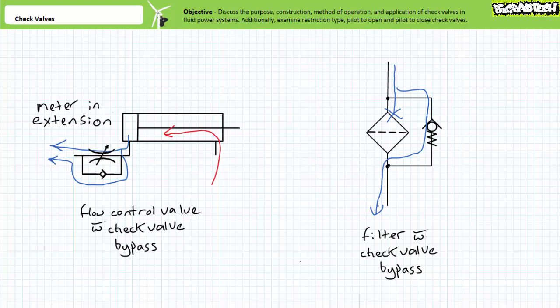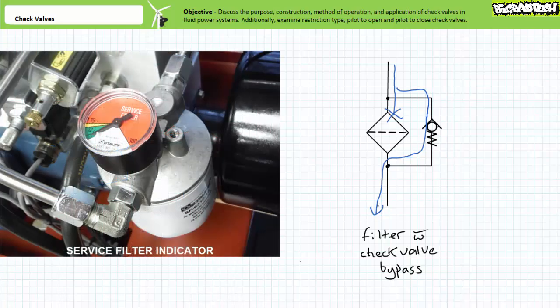The clogged filter bypass check valve therefore allows the system to circumvent the compromised fluid conditioning apparatus and initiate an orderly shutdown. Note the clogged filter bypass check valve ordinarily includes a visual indicator that such event has occurred, and it is incumbent upon the operator and service technicians that such an event be exceedingly temporary in nature.